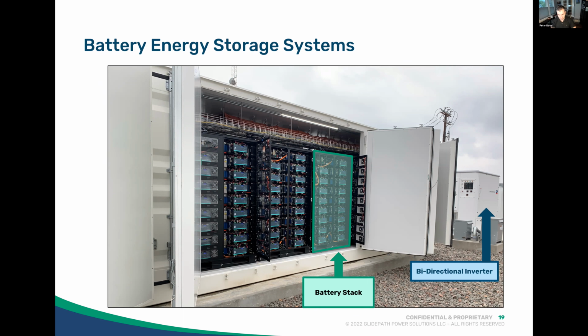I'm almost certain those fans themselves are not monitored. We do monitor temperature within the battery modules. The battery module has several different temperature sensors that look at actual temperature, but also the performance of the battery cells. We monitor and can see thermal issues through voltage. Usually our first warning of a thermal issue is the batteries deviating from the voltage we'd expect, so you'll see the electrical change in performance before you see an actual temperature change. And then we can shut down.